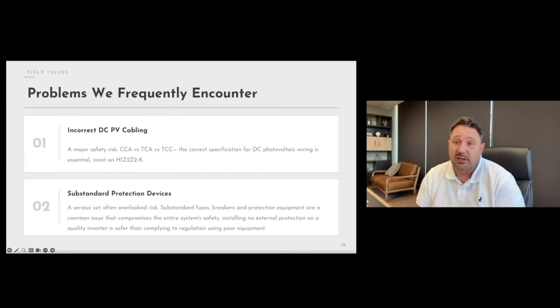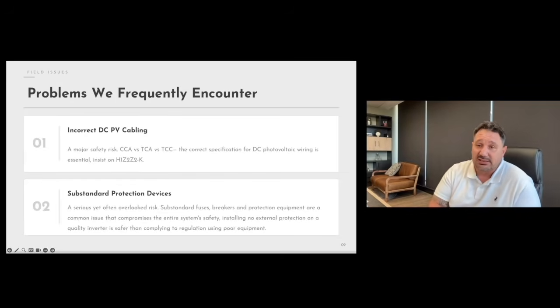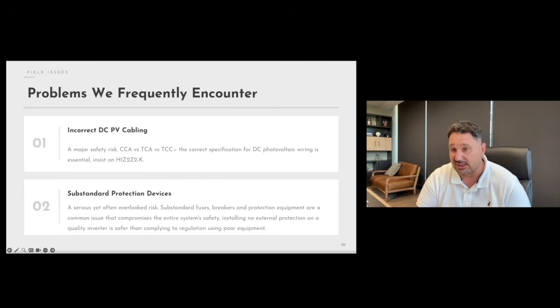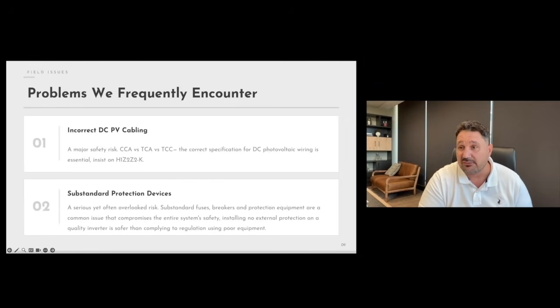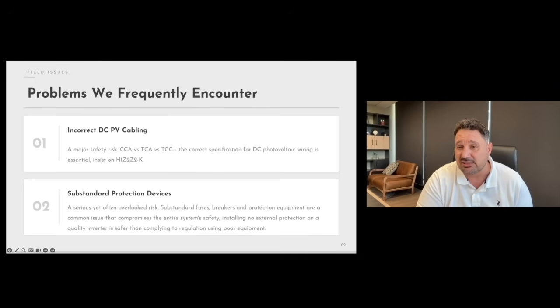The problem we frequently encounter is incorrect DC PV cabling in solar installations. This remains a frequently discussed issue within the industry. It presents a significant fire safety risk, as standard cables are not designed to withstand the high DC voltages, prolonged UV exposure, and temperature fluctuations which PV systems are subjected to. These can result in insulation failure, loose connections, overheating, and ultimately DC arc faults.